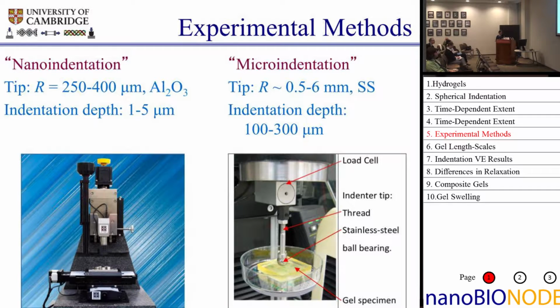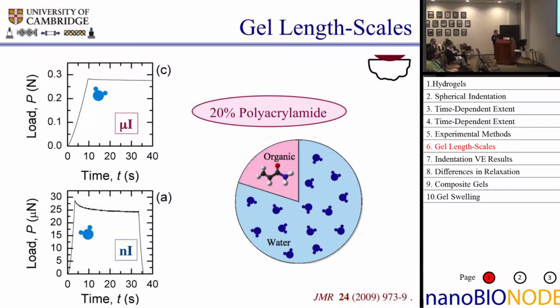So when we do that, I'm going to start here with a reasonably boring and I think actually good candidate for a standardization gel, which is a 20% polyacrylamide. So we chose 20% because that gives it a similar composition to a lot of soft biological tissues, with 80% water. And it's a very formulaic standard thing to make up with recipes. It's pretty repeatable, it's very robust.